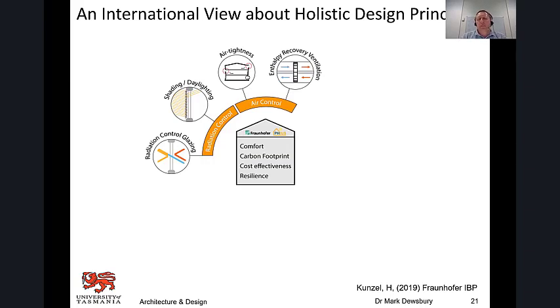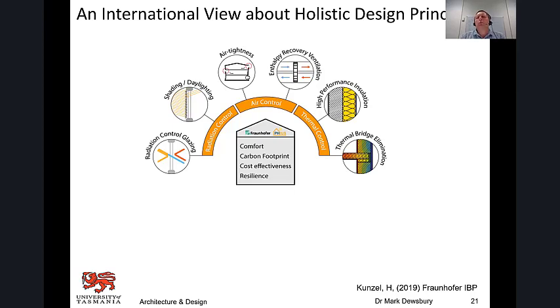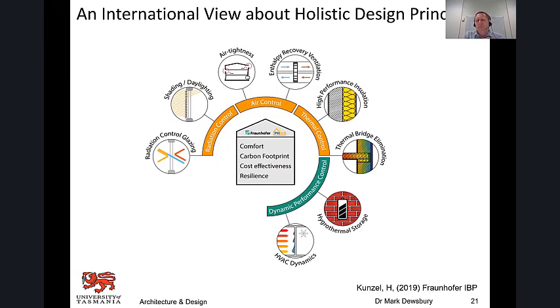The next point, as it gets a bit more detailed, is about how we're considering air tightness and, in terms of conditioning systems, how we think about enthalpy recovery. So whether it's a heating or cooling plant, how we're not wasting the energy we've created in terms of conditioned air, but having a bit more intelligence in our systems. Insulation, well, we know how to insulate, but we're just going to do it better. So the whole thing about how we're providing continuous insulation and how we're addressing thermal bridging properly, not tokenistically. Dynamic performance control. So HVAC dynamics has humidification and dehumidification functions, even the basic split system on the wall. And hygrothermal storage, concrete, all materials in the building, every single material absorbs and releases, so more thermal mass.